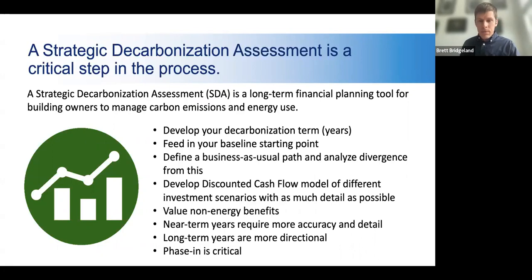Because this stuff isn't going to happen through incremental, short-payback, traditional audit-driven energy efficiency improvements like we've seen in controls or LED lighting. What this means is mapping out pathways—maybe a decision tree with options that get to full decarbonization—and mapping the triggers for when those enabling steps can occur, so it becomes more feasible to wean off gas or fossil-fueled district steam heating solutions.